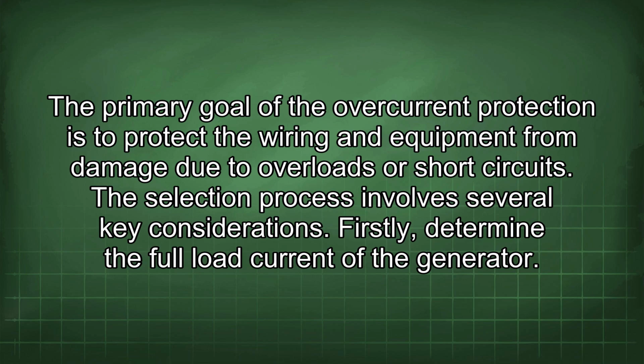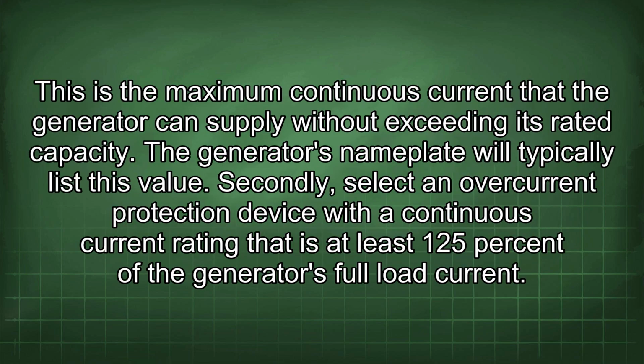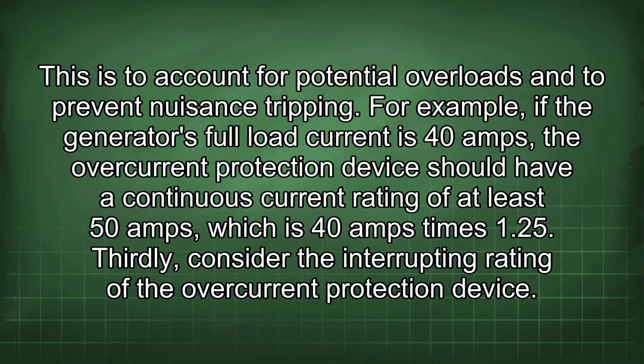Firstly, determine the full load current of the generator. This is the maximum continuous current that the generator can supply without exceeding its rated capacity. The generator's nameplate will typically list this value. Secondly, select an overcurrent protection device with a continuous current rating that is at least 125% of the generator's full load current. This is to account for potential overloads and to prevent nuisance tripping. For example, if the generator's full load current is 40 amps, the overcurrent protection device should have a continuous current rating of at least 50 amps, which is 40 amps times 1.25.